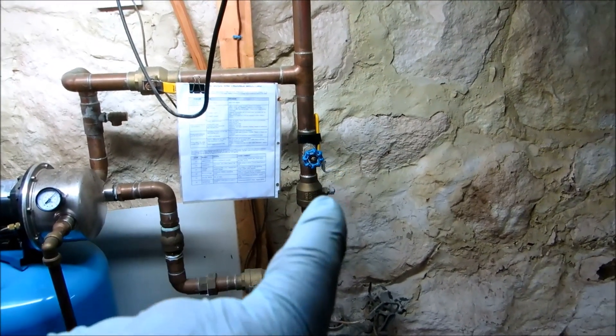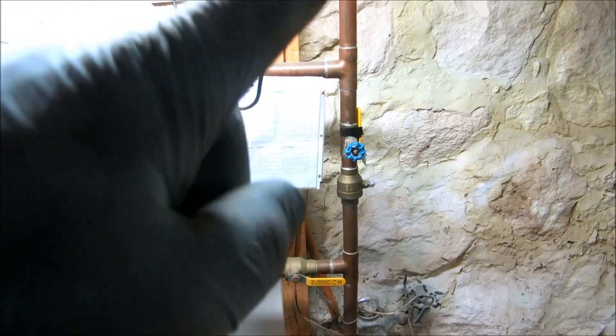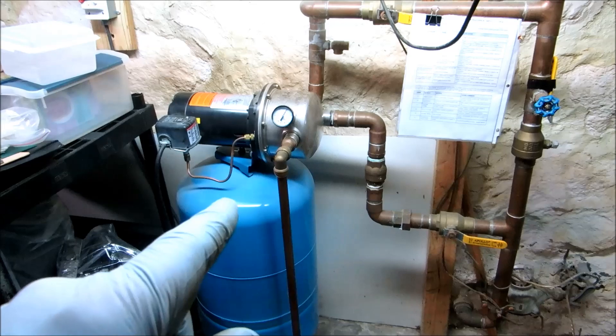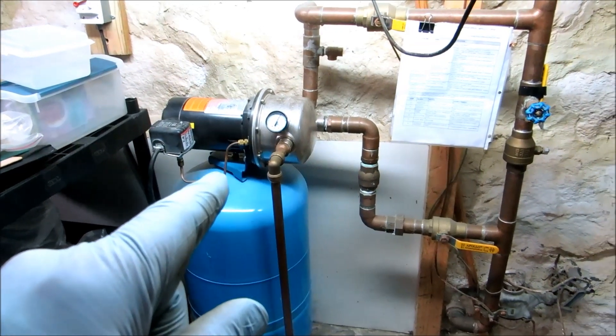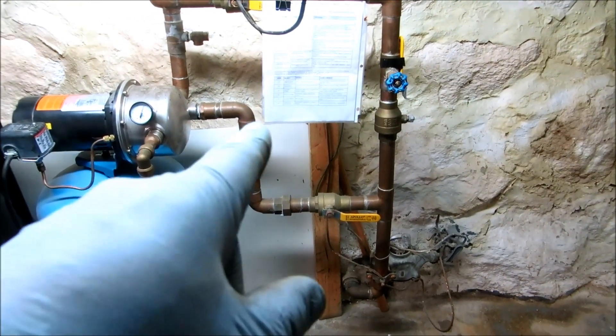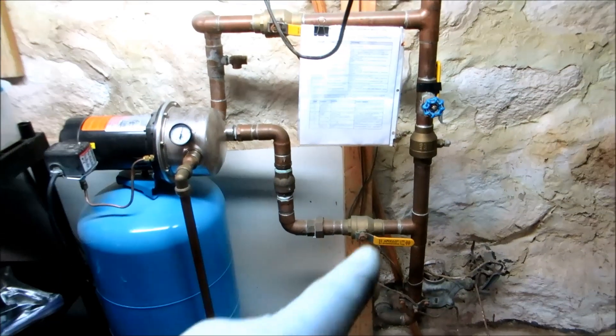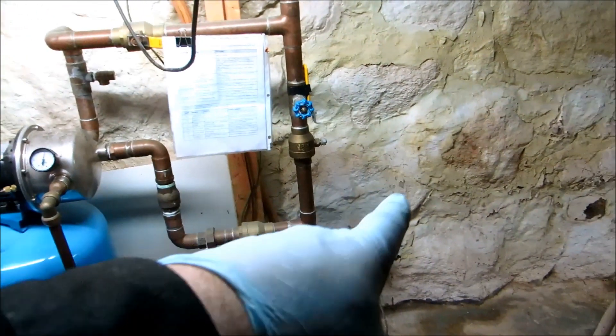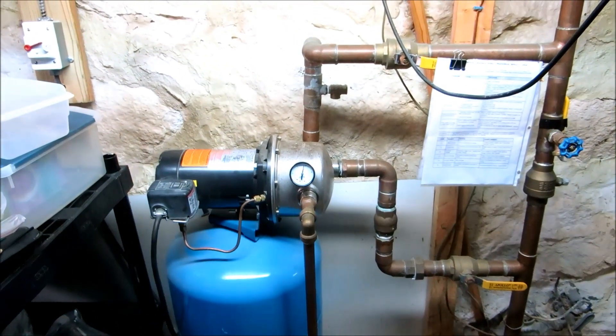I took that handle off. Now the water comes in, gets pumped up, and goes up to the building with the pressure. I just checked upstairs and people are doing showers and using the water. It can't go back into the main because of the check valve. We don't have any double checks on the water meters. Before I got here, that valve was open — they were pumping up water but pressurizing the water main in the town. It's working now.